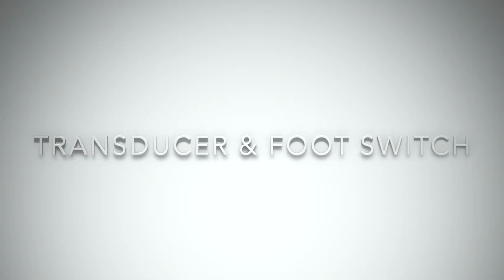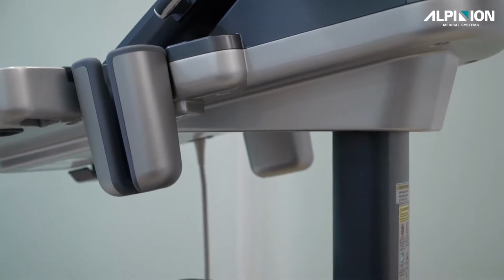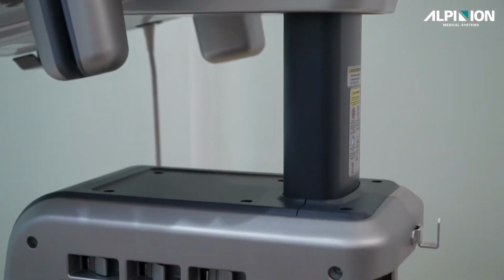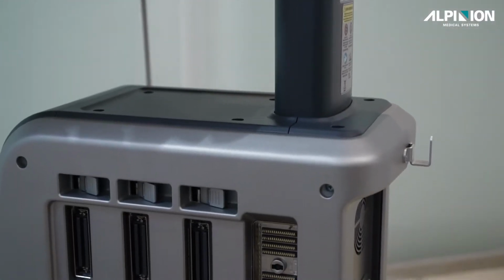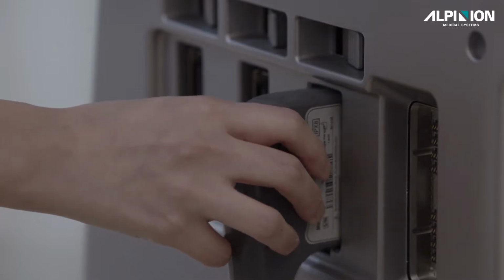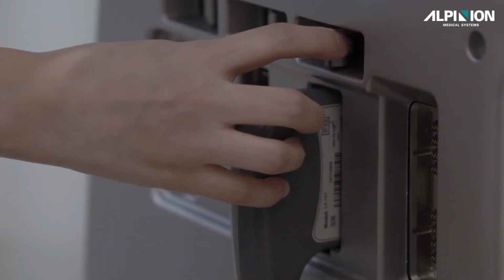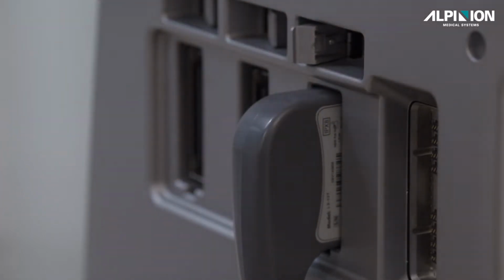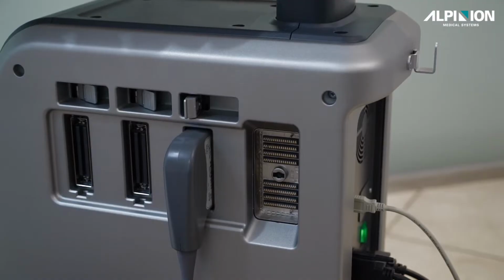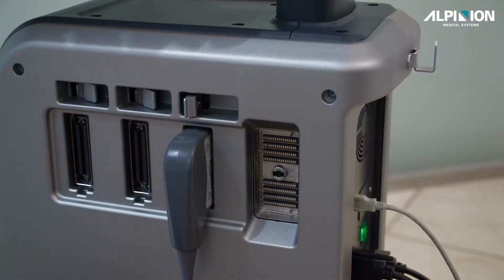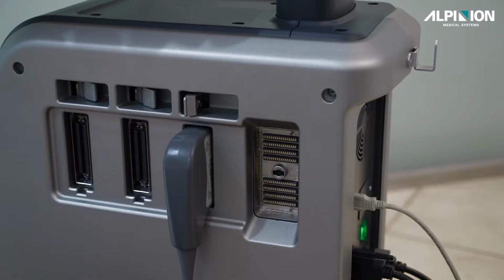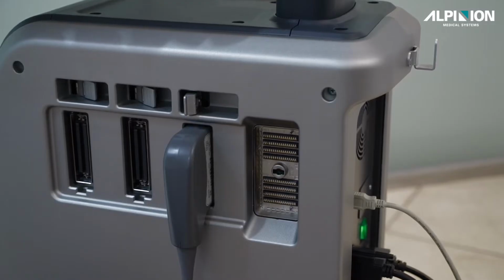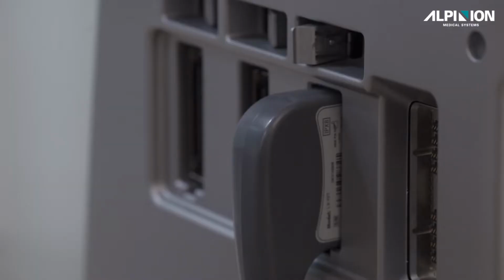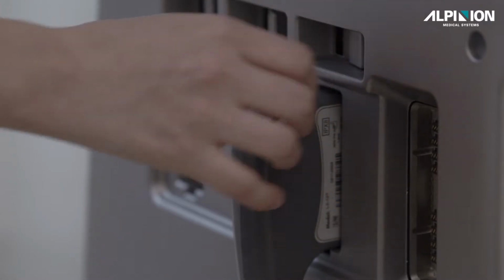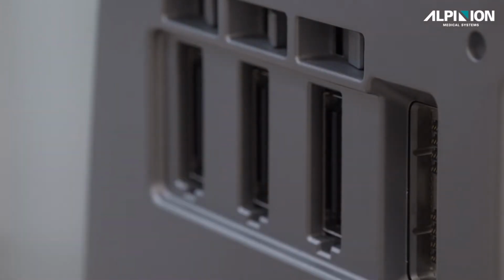Part 2. Transducer and Foot Switch. You can connect your probe on the right side of your system. To connect your probe, you will insert the probe into one of your probe ports and lock it by pressing up on the lever. And to disconnect the probe, first make sure that you press the freeze key before disconnecting, and then you can depress the lever to unlock and pull the probe out of the connector.